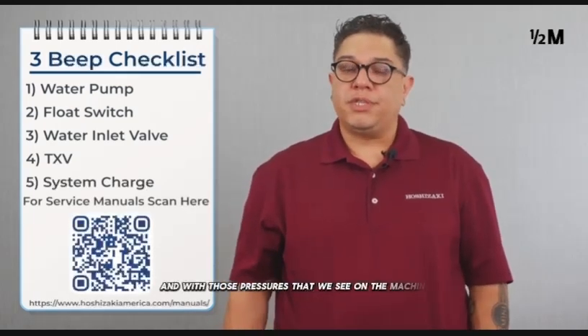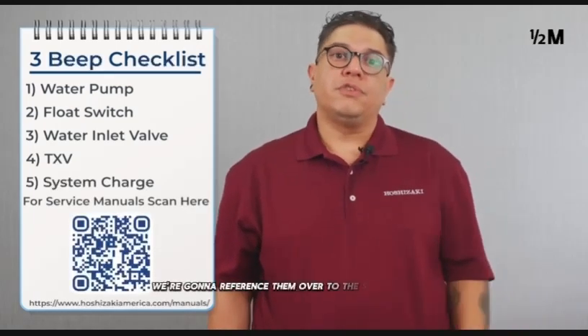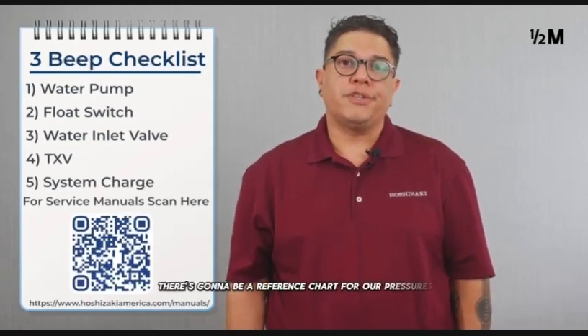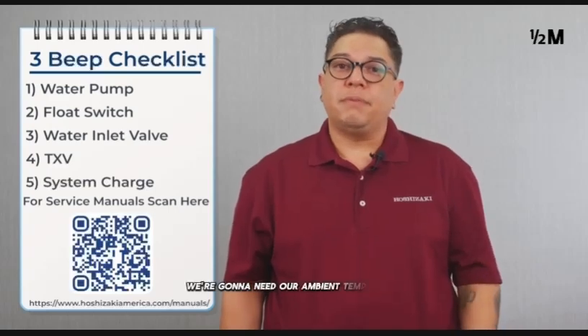We're going to check the pressures 5 minutes into the freeze cycle. And with those pressures that we see on the machine, we're going to reference them over to the service manual. In the service manual, there's going to be a reference chart for our pressures. We're going to need our ambient temperature and our water temperature to be able to find the right pressures for that machine.